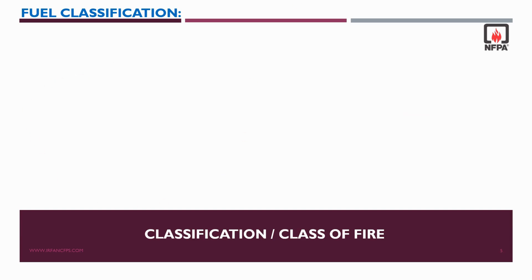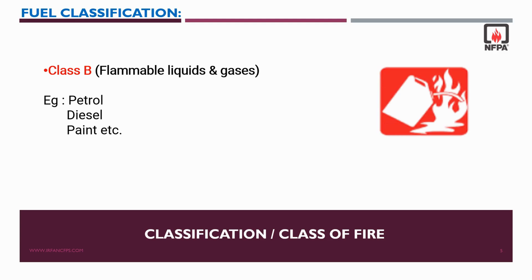Class B fires are fires in flammable and combustible liquids and flammable gases. For example, petrol, diesel, paints, oil-based paints, petroleum greases, solvents, alcohols, tars, oils — everything comes under Class B fires.